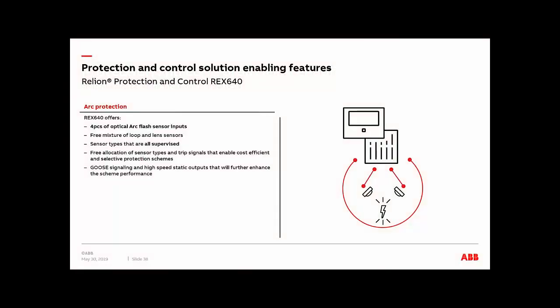Okay, when it comes to protection and control solution enabling features, we talked about the arc flash. It's important to mention here, we got the 4 pieces of arc flash sensor inputs. This is optional when you order the relay, and you got a mixture of loop or point sensors. Now, the free allocation of sensor types is going to give you a cost-efficient protection scheme. It is important to mention that the relay still does analog to digital conversion, so you will still lose a little bit of speed there, but nonetheless, you're still using the high-speed outputs. You will get a fast response for arc flash schemes there.